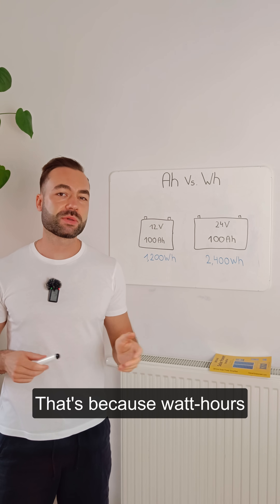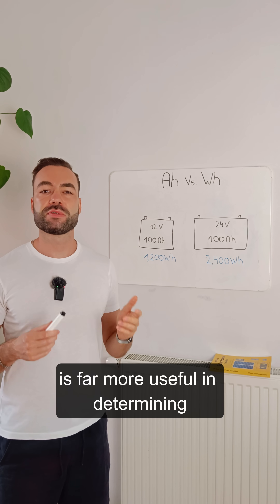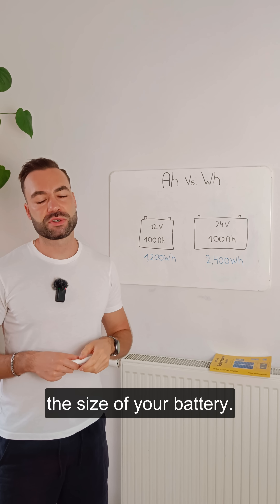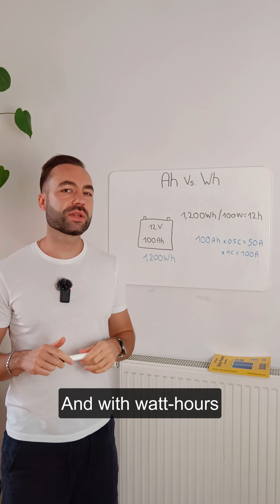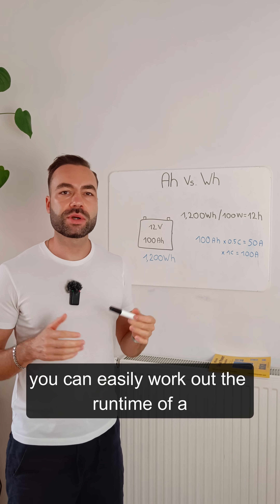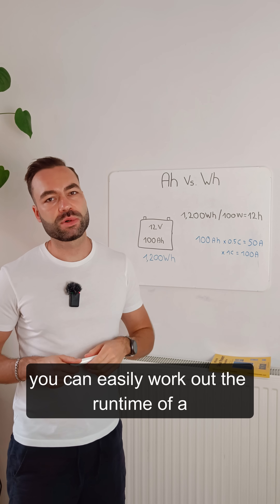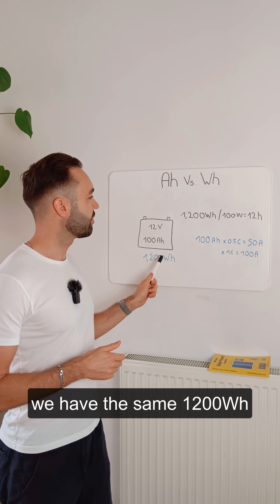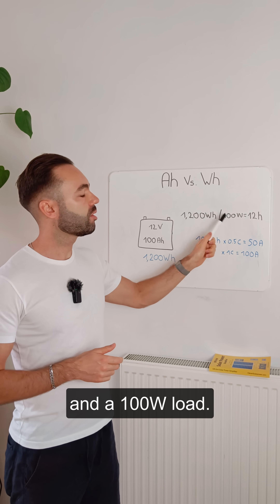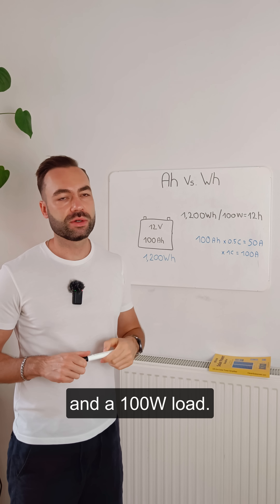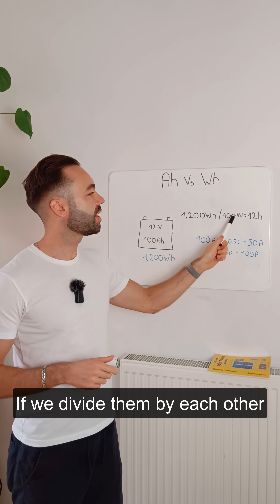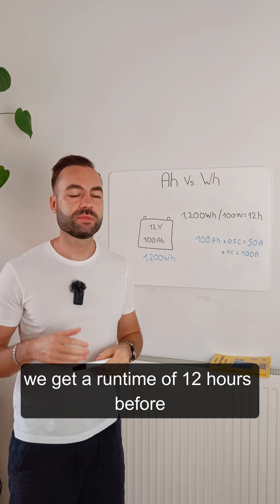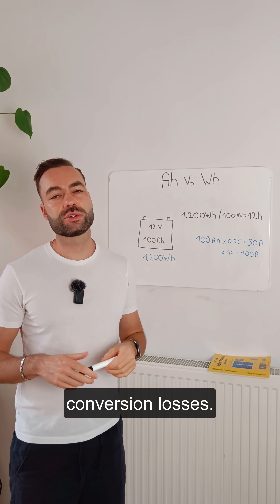That's because watt hours is far more useful in determining the size of your battery. With watt hours you can easily work out the runtime of a device. Let's say we have the same 1200 watt hour battery and a 100 watt load — if we divide them by each other we get a runtime of 12 hours before conversion losses.